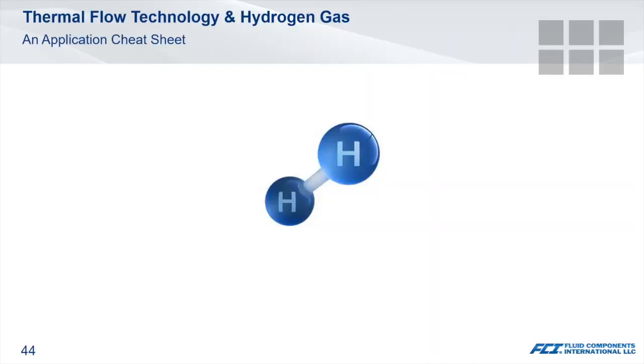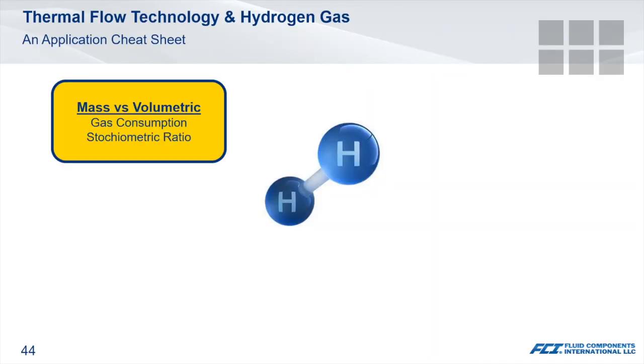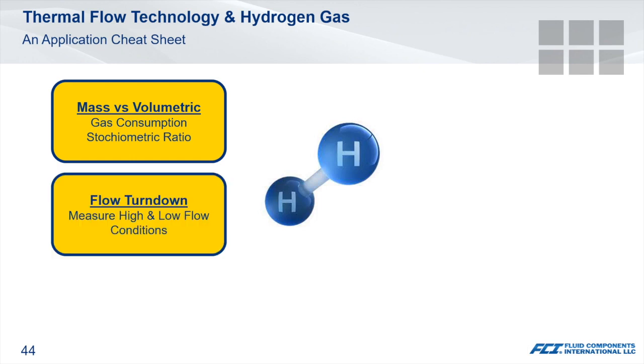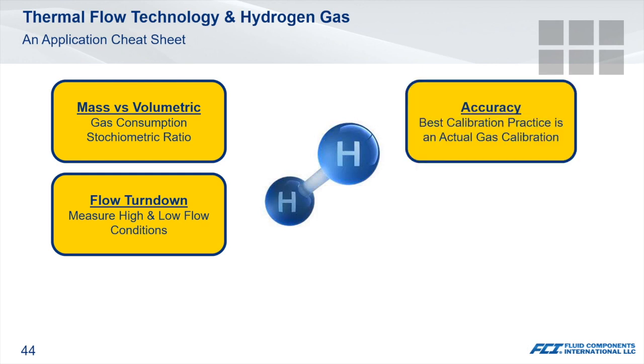To summarize, utilize mass flow meters instead of volumetric meters to better understand your production capacity or optimize your process control. Evaluate and select a technology that ensures you meet both the high and low flow conditions of your process. Actual gas calibrations ensure the best results. Using a calibration equivalency can introduce additional measurement error.